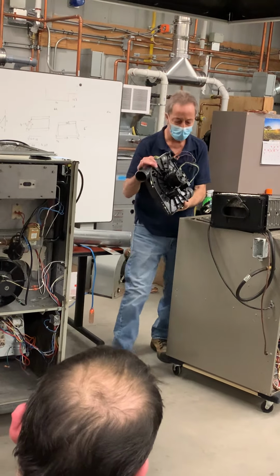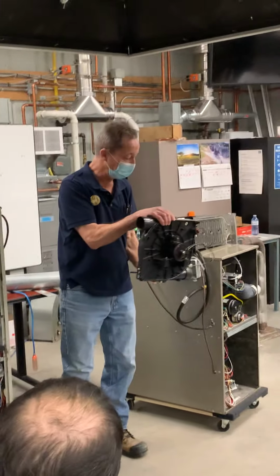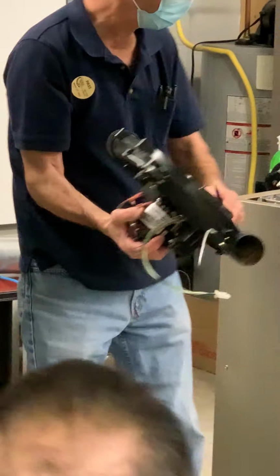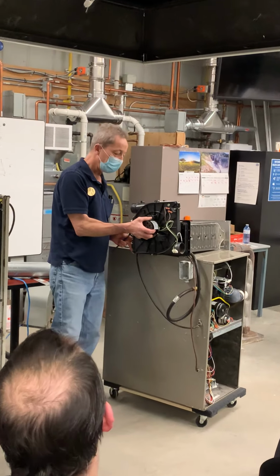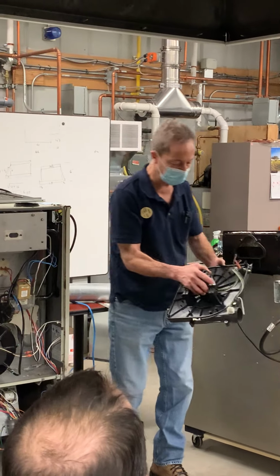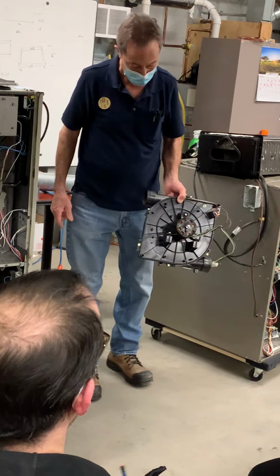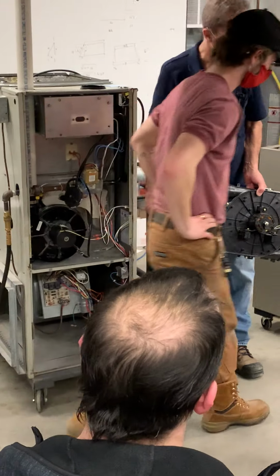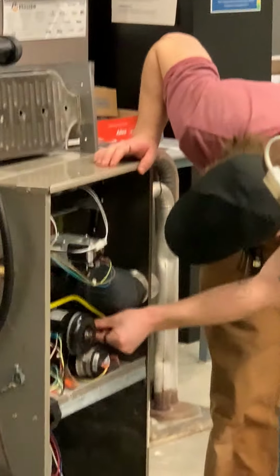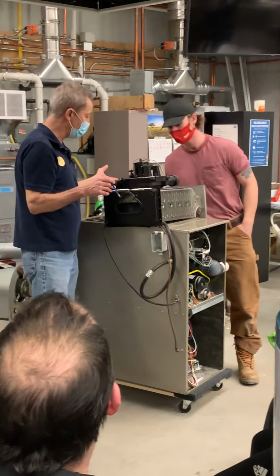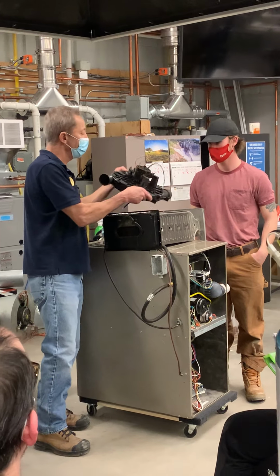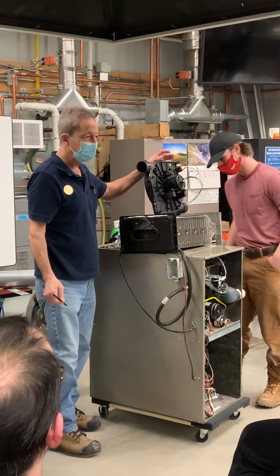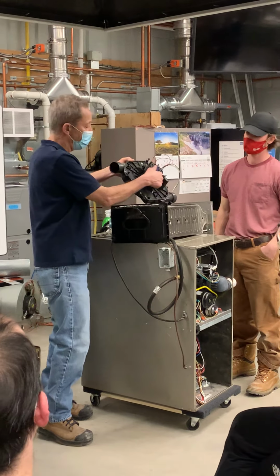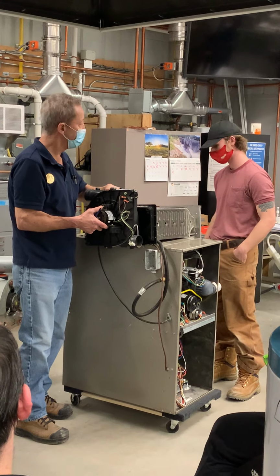This is a typical inducer assembly out of here. So you see the triangular shape here? That lines up with this. So when this goes out there, it sucks. Where's the pressure switch attached on this one? You can have a look at it. Like this big square. Yeah, that square tube, which fits onto this. Now, depending on the model, it can fit on different spots, okay? So it's sensing the negative pressure thanks to the inducer. So when this sits on here and it runs, it sucks. It makes a negative pressure.